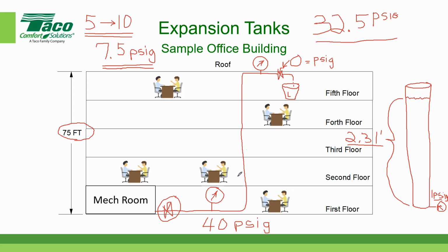Yeah, so initially we said there was nothing in this pipe, and I had a device here, a valve, that allowed me to add water to this piping system. And let's say the water ultimately came from the city, and the city water out here in the street, there's a pipe in the street, and let's say that pressure in the street was 80 PSIG. Well, somewhere in my mechanical room, I have to have a fill valve with a pressure regulating valve. So inside there, I have a pressure regulating valve.